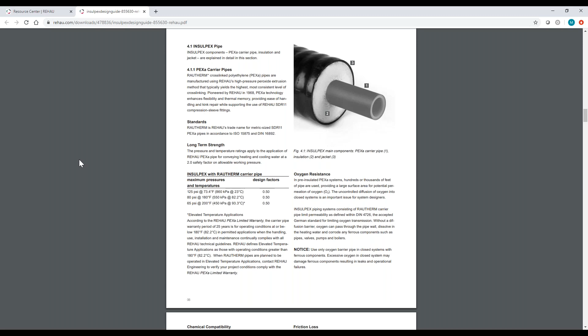Yeah, so it's a pentane blown polyurethane foam, and there is some element called outgassing, where the gas leaves the polyurethane foam over a prolonged amount of time. There's an equation you can run that gives you an idea of how much degradation there is over time. This system's closed in the sense that we don't see a lot of that. We have projects we've started, and 15 years later we're adding on to, and the foam, aside from being a little yellowed, is still intact.